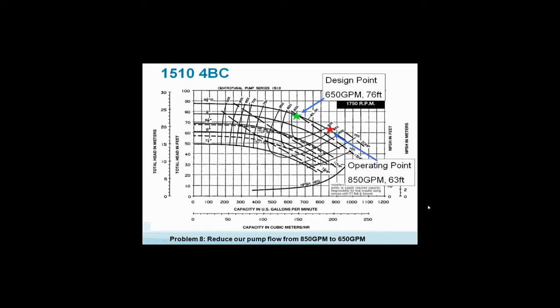So how do we balance this? How could the system sizer help us? What can we do? Well, remember that scale 5 on the B&G system sizer of the manual one, or the CD charts in the Windows-based version, where you put in the known and unknown flows and heads. That's where these square charts come in handy. We're going to plot a system curve. We're going to put a system curve on this and see what happens. Reality, we're flowing at the red star. That's the real system curve. The green star is where we thought it would be, but it's not there.